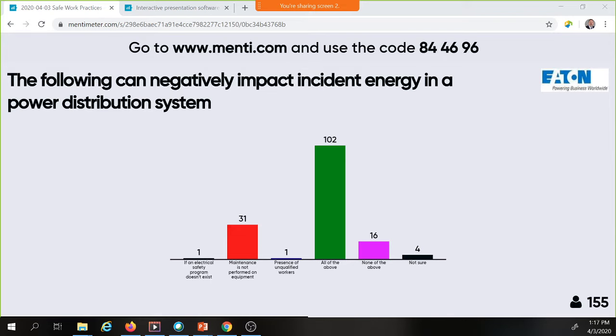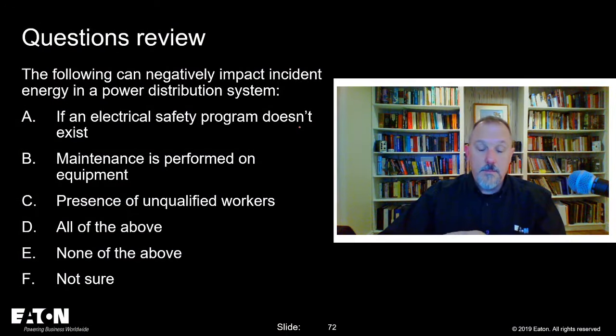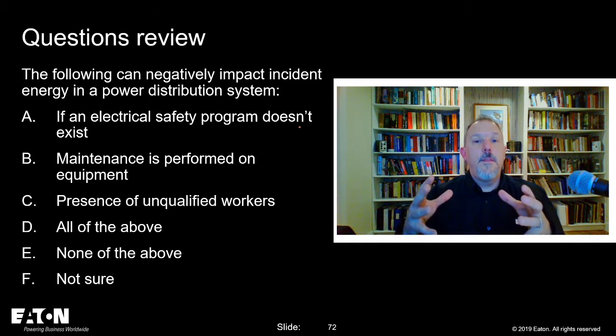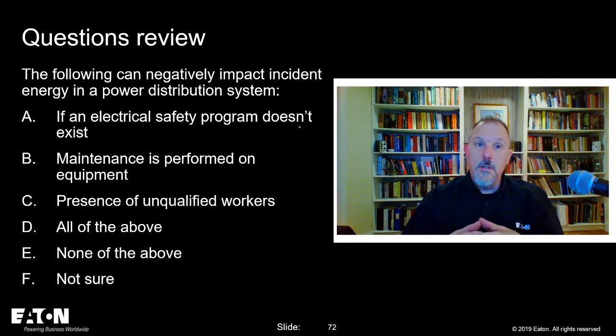I'm feeling pretty sure. And if an electrical safety program doesn't exist, that really can't impact the incident energy, because incident energy is what it is. What are the two key components of incident energy? Current and time. What impacts incident energy? What impacts the current and time aspect of incident energy? It's how long it takes me to clear the circuit when an arc flash event occurs.